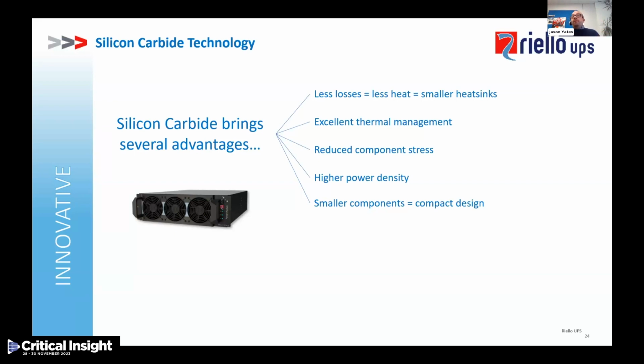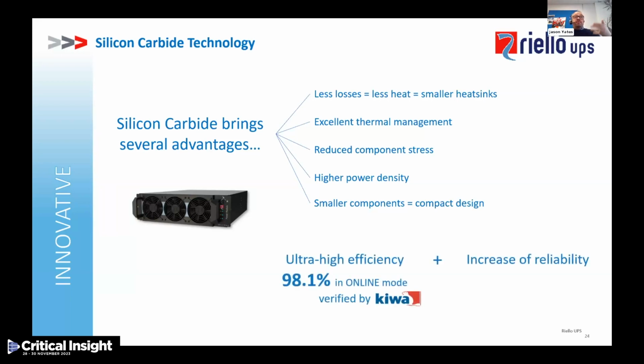They have a very high power density because of their size. And because of the smaller components, it equals a compact design. And because we can do this, we've now got ultra high efficiency UPSs pushing 98.1%, again, independently verified. And also we have increased reliability, which is obviously extremely important with any UPS system.